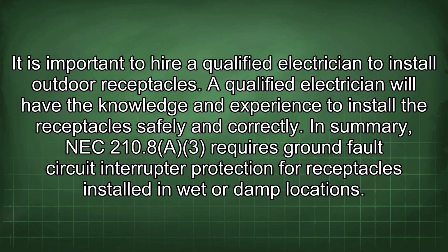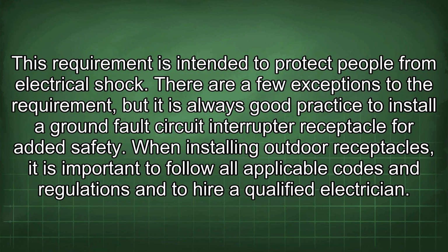In summary, NEC 210.8(A)(3) requires ground fault circuit interrupter protection for receptacles installed in wet or damp locations. This requirement is intended to protect people from electrical shock. There are a few exceptions to the requirement, but it is always good practice to install a ground fault circuit interrupter receptacle for added safety. When installing outdoor receptacles, it is important to follow all applicable codes and regulations and to hire a qualified electrician.